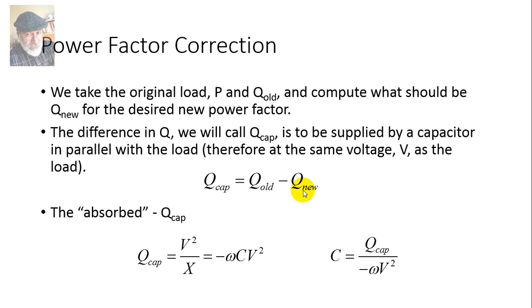We are content with saying we need so many kilovars of capacitance to compensate and correct the power factor. But if we insist on finding the value in farads for the capacitor needed, added in parallel to the load, to bring the power factor up to a certain value, then that is the Q cap needed divided by the negative of omega times the RMS volts squared of the factory.